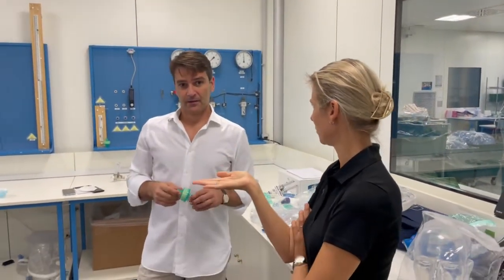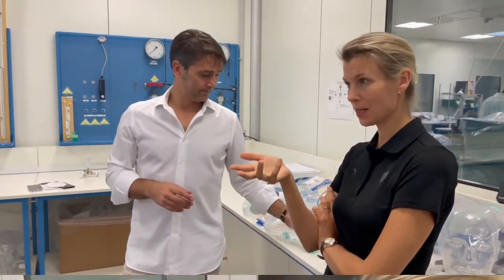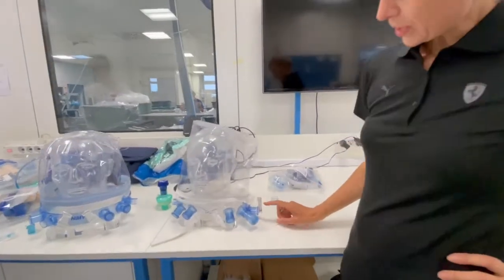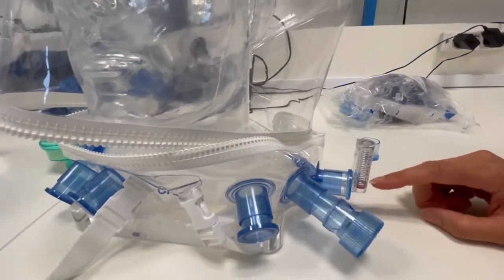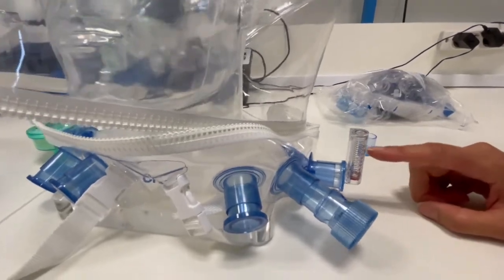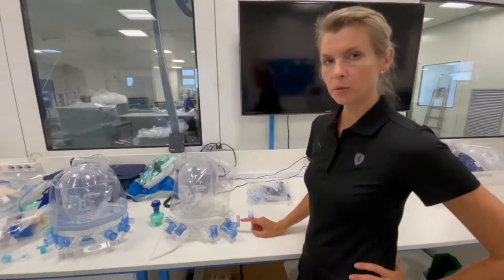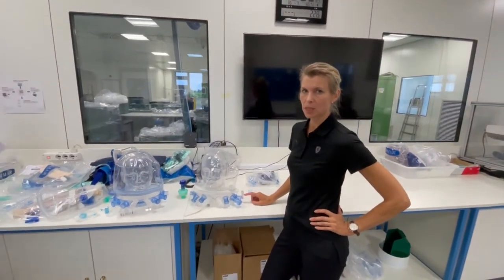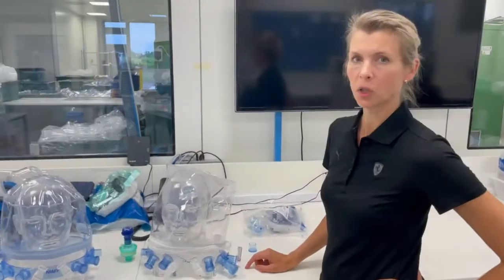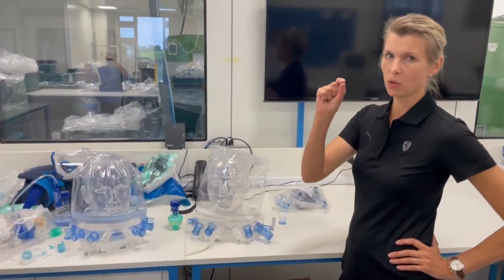The pressure will depend on the flow you are giving to the patient. This is only for the helmet CPAP setup. What is nice about the manometer is that you will know if there is too much fluctuation in pressure when the patient is inhaling and exhaling — meaning there is not enough flow in the helmet — so you want to increase the flow to make that fluctuation as low as possible.